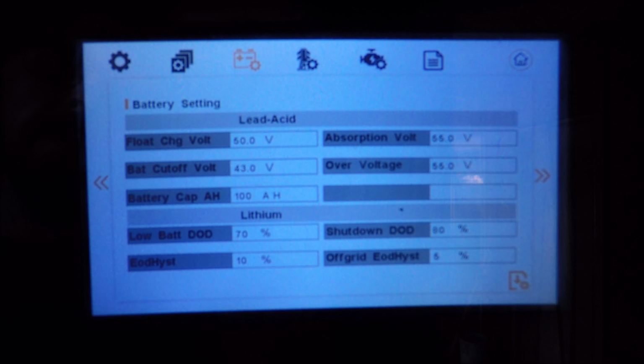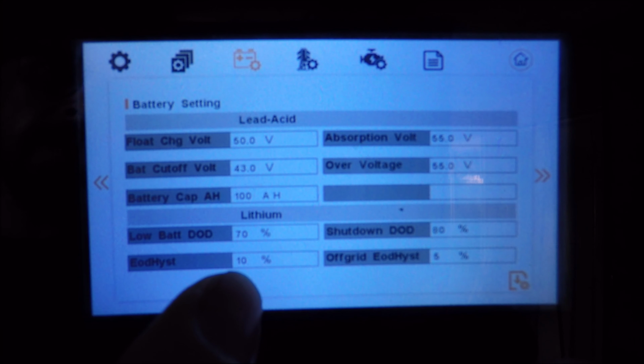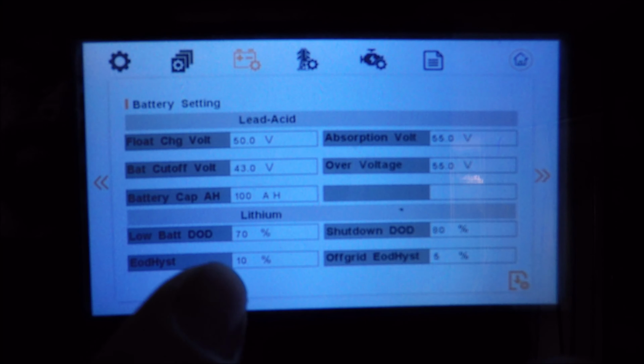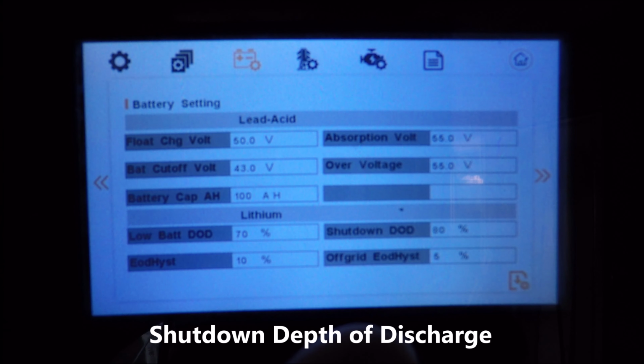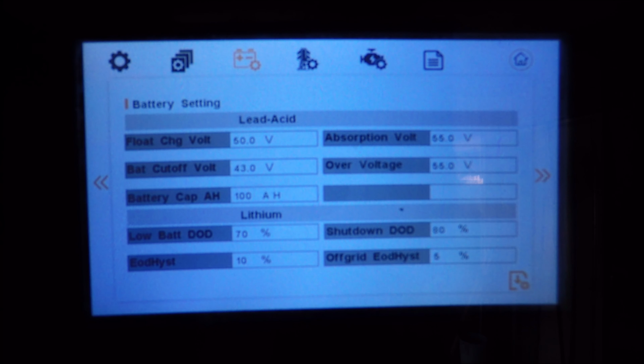What that means is the alarm will go off that you've hit your low battery depth of discharge, but it will not stop the alarm until you reach 40%. So 70% here means there's 30% left in the battery. A 10% hysteresis means it has to get to 40% before your low depth of discharge alarm ceases. Shutdown depth of discharge, we'll set this to 90%.